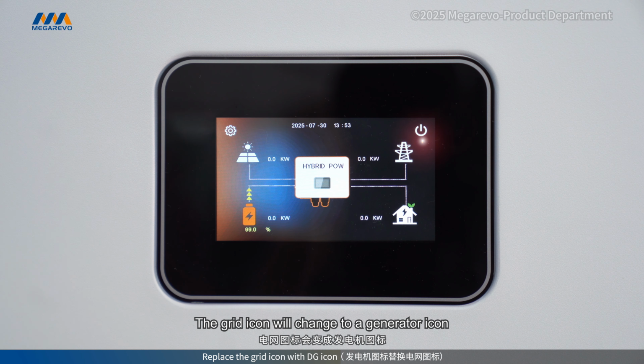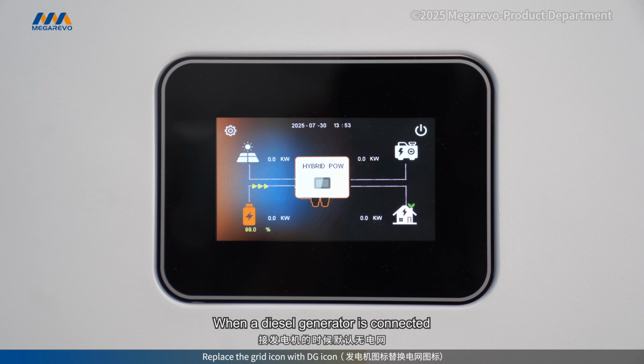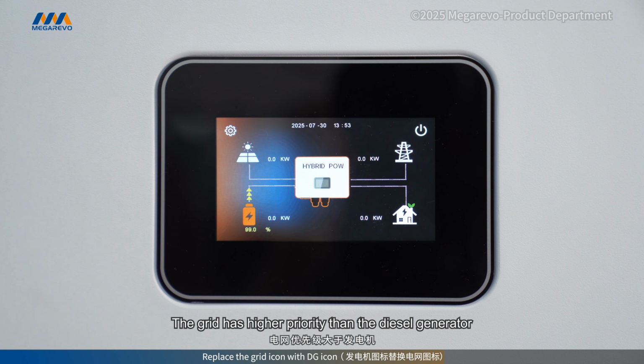The grid icon will change to a generator icon. When a diesel generator is connected, the system assumes there is no grid by default. Once a grid is detected, the generator is automatically disconnected, and the grid icon is displayed again. The grid has higher priority than the diesel generator.